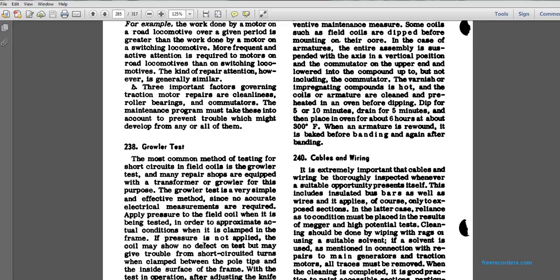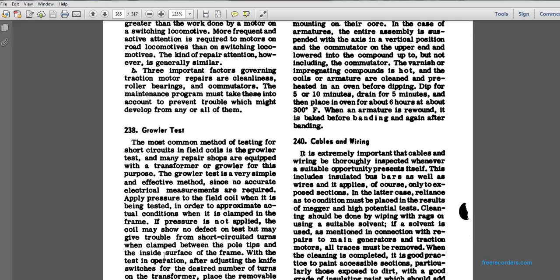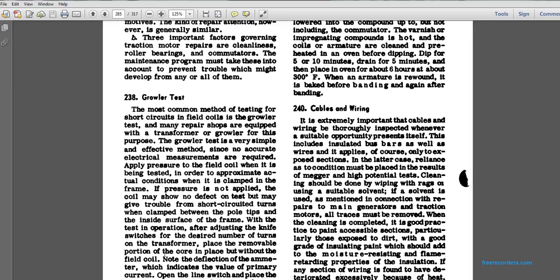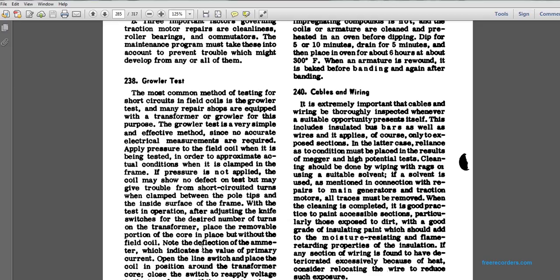If pressure is not applied, the coil may not show a defect on the test, but may give trouble from short-circuited turns when clamped between the pole tips and the inside surface of the frame. Start the test operation after adjusting the knife switches to the desired number of turns on the transformer. Place the removable portion of the core in place but without the field coil. Note the deflection of the ammeter. When it indicates the value of the primary current, open the line switch and place the coil in position around the transformer core.